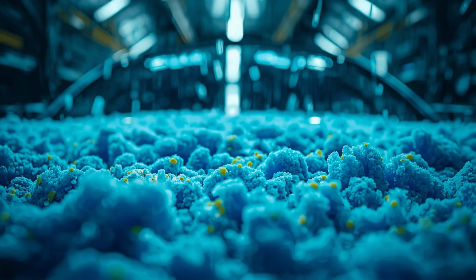At midnight, when the last customer has departed and the facility enters its nightly shutdown mode, a different kind of activity begins. This is the automated cleaning cycle, where the car wash essentially washes itself. The PLC initiates this process automatically based on its internal clock. All vehicle washing operations cease, but the equipment systems remain active. The high-pressure pump continues to run, but now its output is directed through a different set of nozzles, self-cleaning nozzles mounted throughout the tunnel that spray water and cleaning solution across all internal surfaces.